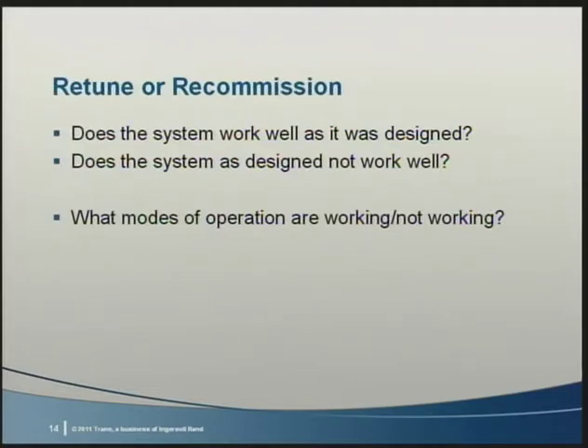Perhaps humidity control is a challenge, but only at part load. This can be exacerbated if the system is oversized, or if too much chilled water reset is being used. What situations trigger the problem? You may have a short amount of time to go from unoccupied to occupied mode. If the system is too small or the changeover not anticipated, you may think the system can't handle the loads. Think of a church that's mostly unoccupied all week. Can you pull the environment back to the occupied state fast enough?